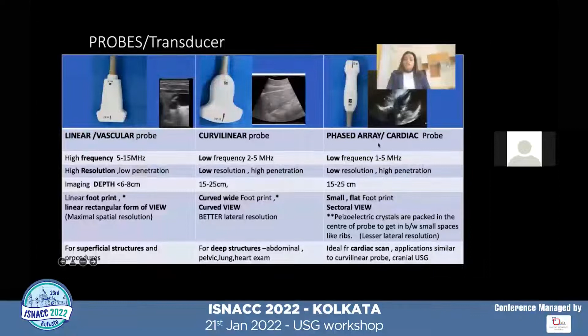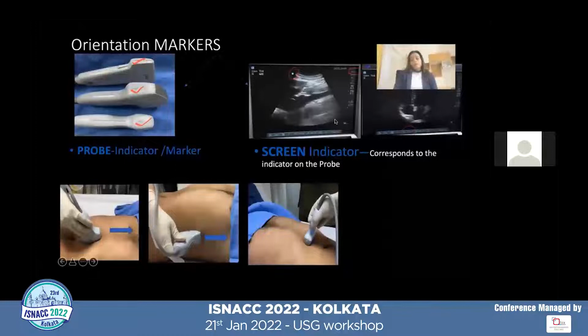Coming to the orientation markers, they help us in the orientation of the image. So there are markers on the probe as well as on the screen. The probe indicators are present on one side of the probe, as you can see in the image, and by default the markers are kept pointing towards the head end or towards the right side of the patient. And there is a screen indicator which corresponds to the indicator on the probe. And you see here that in all general applications and procedures, the screen marker is on the left side of the image. But in case of cardiac scan, you can see here, the probe marker is always on the right side of the screen.